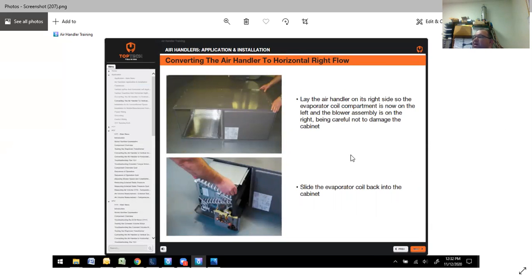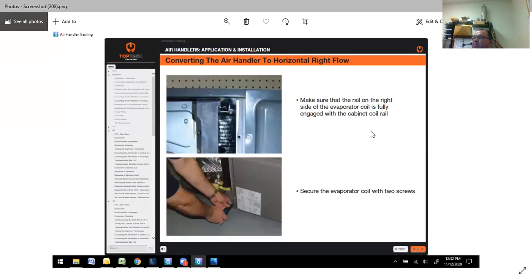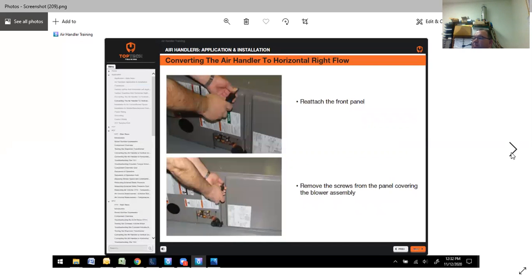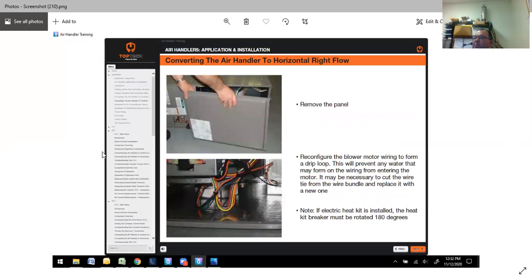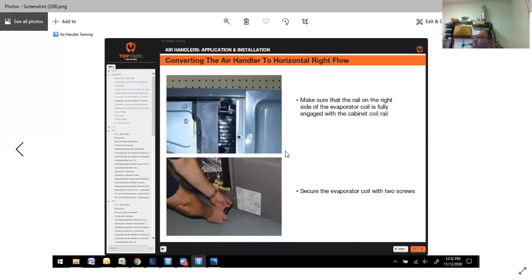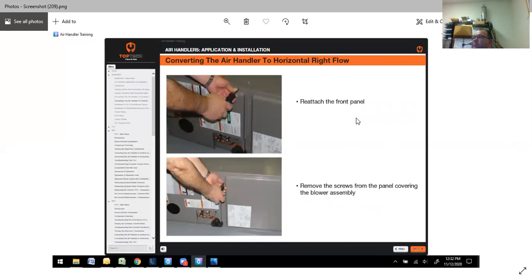Lay the air handler on its right-hand side so the evaporator coil compartment is now on the left. Be careful not to damage the cabinet. Slide the evaporator coil back into the cabinet. Make sure that the rail on the right, see right here, is fully engaged with the cabinet rail. Once it's in there, secure the evaporator coil with 2 screws. Reattach the front panel. Remove the screws from the panel covering the blower assembly. Oh, let me back up here. Kind of jumped ahead. So secure the evaporator coil with 2 screws. Reattach the panel. You're good to go.